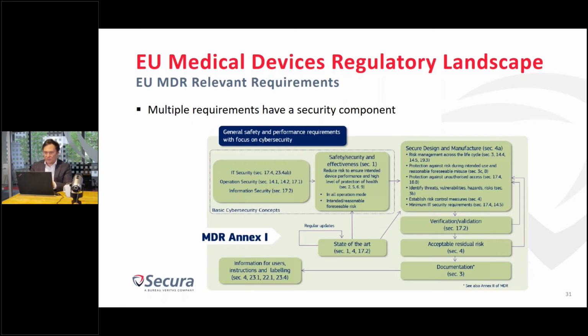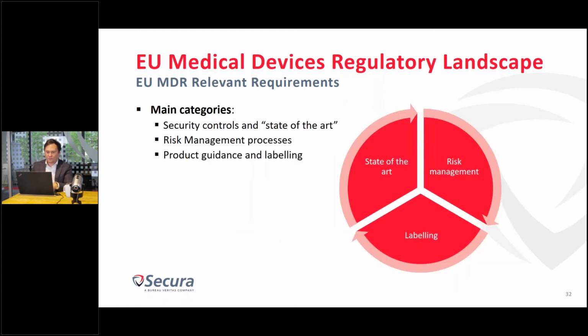This diagram is taken from the guidance document as well, and over the next slides we will summarize the main topics and requirements that need to be taken into account for the medical device regulation. Those main requirements could be split into three items: security controls and state of the art embedded into the medical device, requirements dealing with risk management processes into the product itself, and requirements dealing with product guidance and sufficient labeling included into the device.